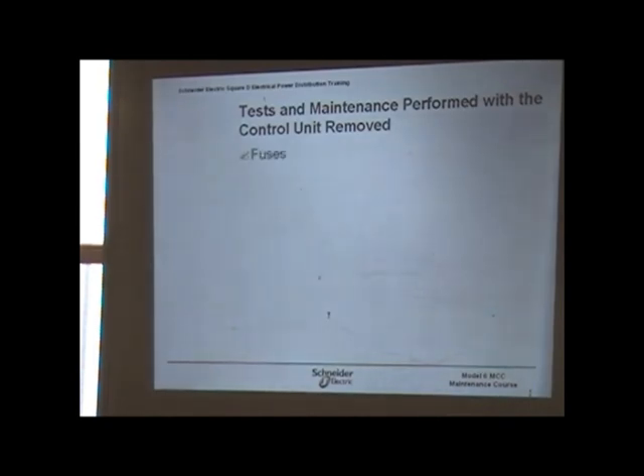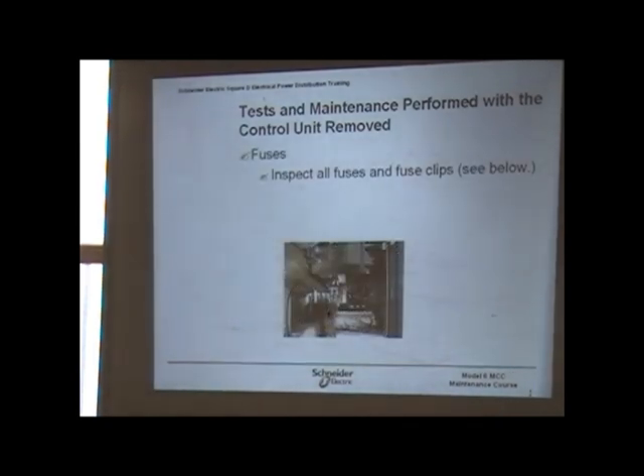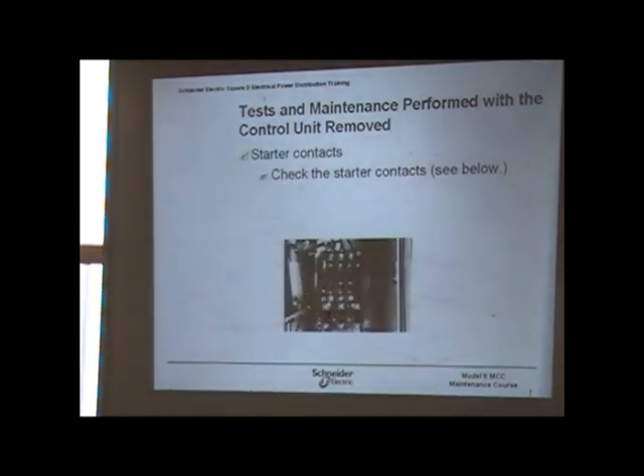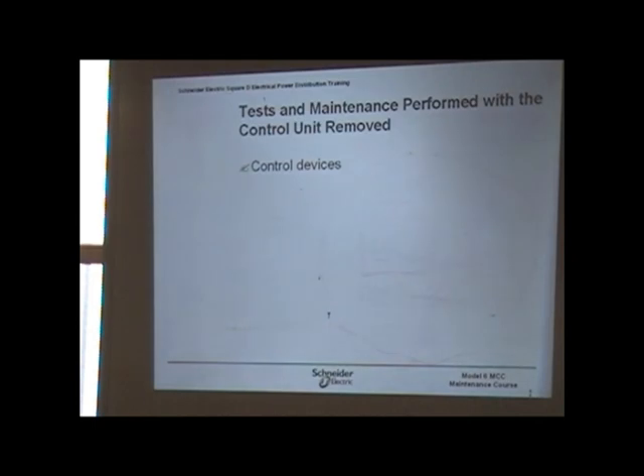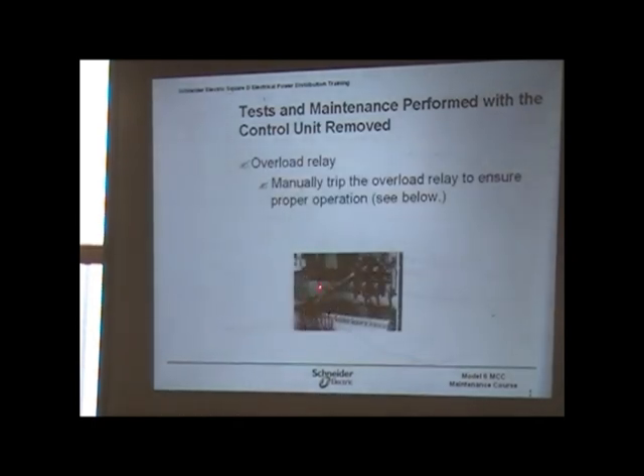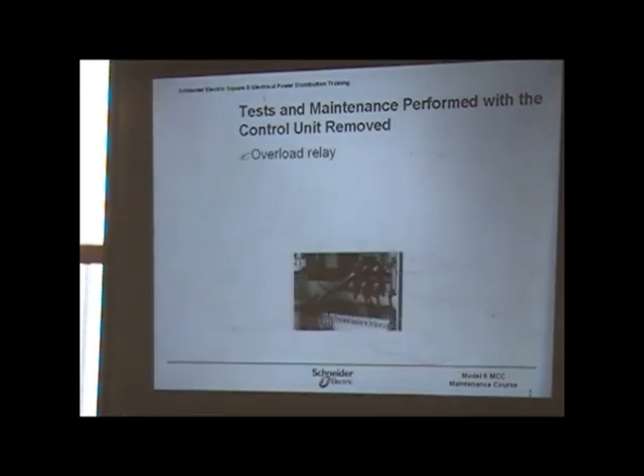I can't say it enough, folks, you just have to be careful with this stuff. The fuses and starter contacts, this stuff is very basic. So if you stick your hands in there, please make sure there's no voltage on the secondary, right here at the bottom side of that breaker. Because now you're messing with these contactors, and if it's energized up top and you close those contacts, you're toast. You've got 480 coming right across there.